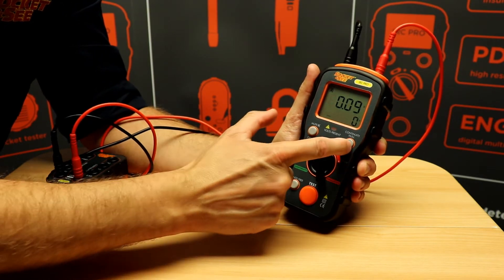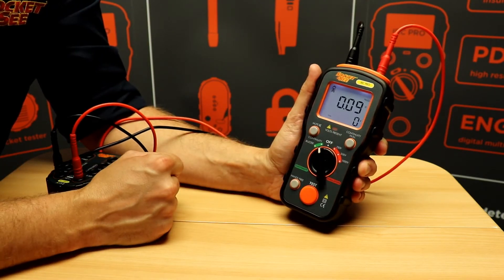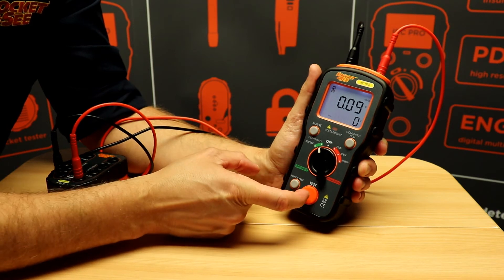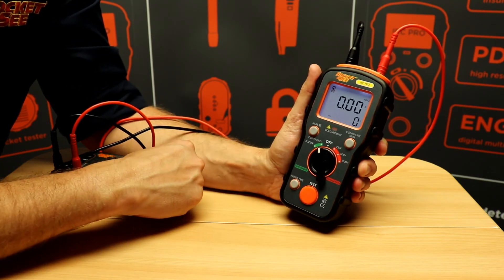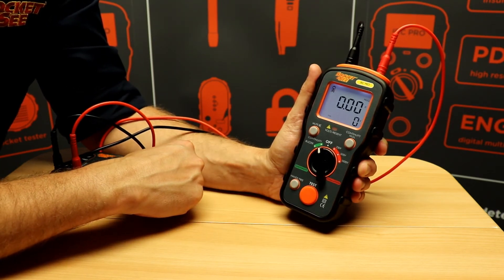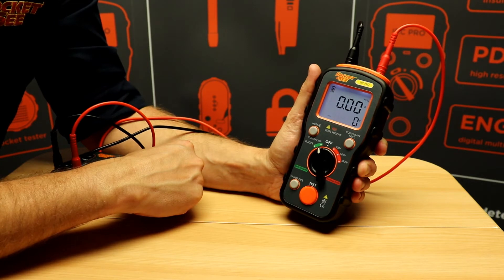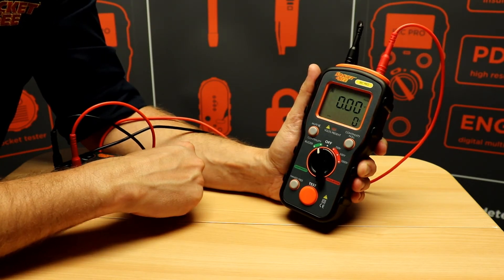To get rid of this value of the test leads we'll press Continuity Null. That takes into account that resistance so if we do a test it's then zeroed our results. This null value will be remembered until another Continuity Null test has been carried out.